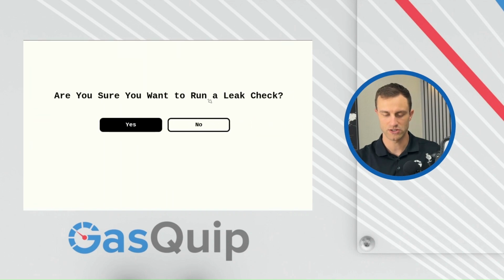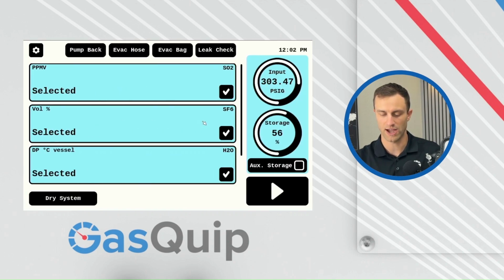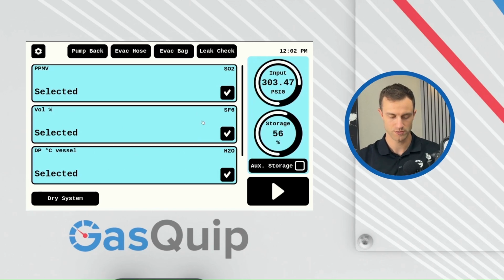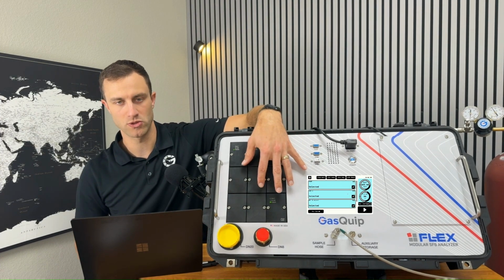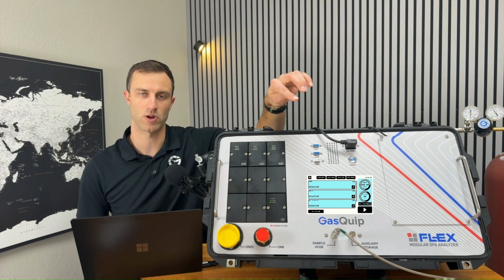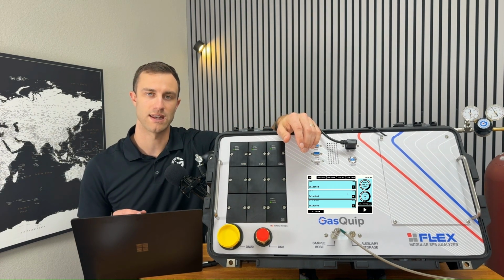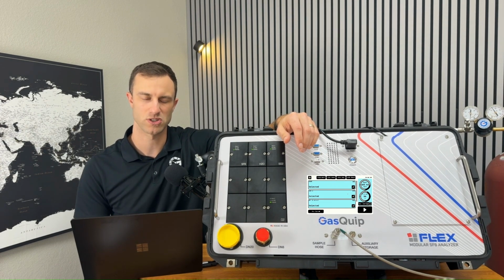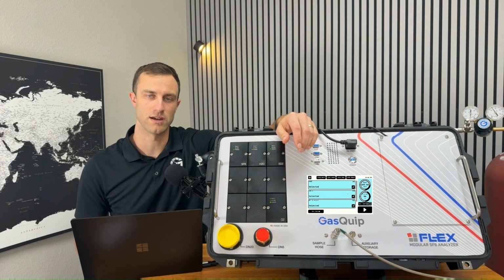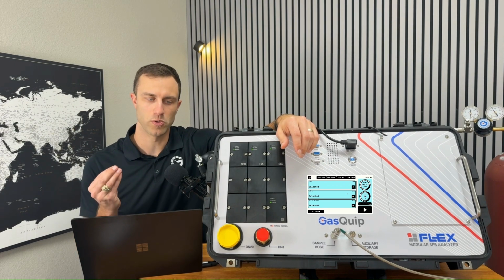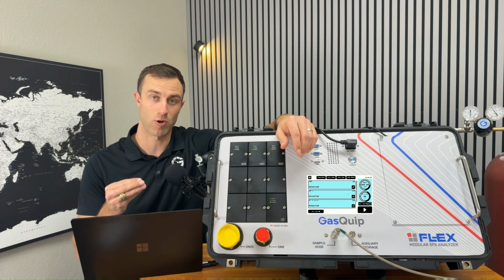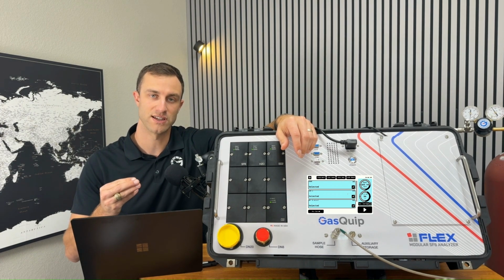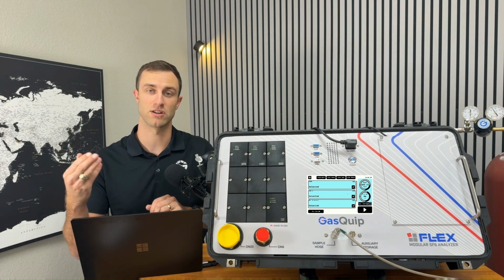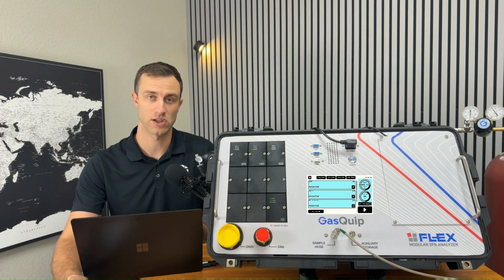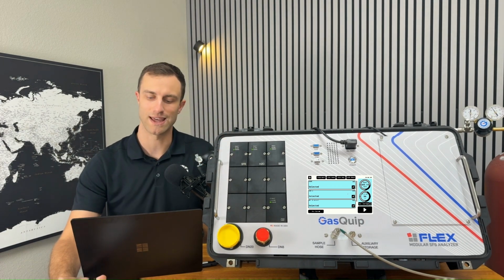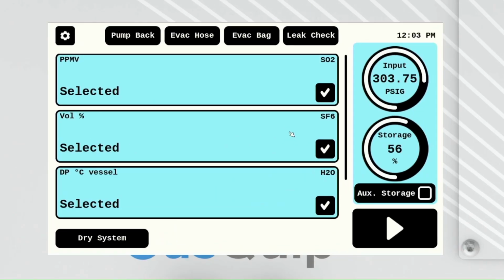Your leak check function is going to pull an evacuation on all of the modules. So evacuation gets pulled on all the installed modules and all the plumbing that runs from the pump to the modules. And it's going to hold that for 10 to 15 seconds, much like the leak check on the evacuation of hose function. It's going to pull evacuation, watch for a rise in pressure, and if it doesn't see that rise, then it'll pass the test. And if it does, then it'll tell you that you have a leak, and it'll actually tell you which module position you have the leak in. So very helpful to troubleshoot.